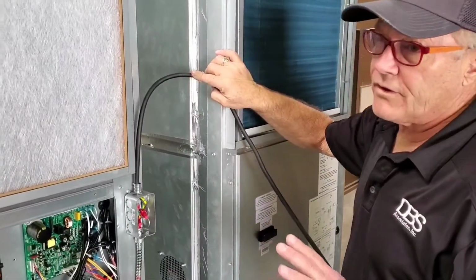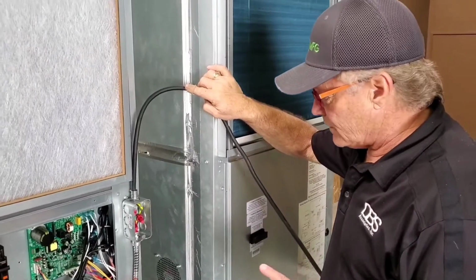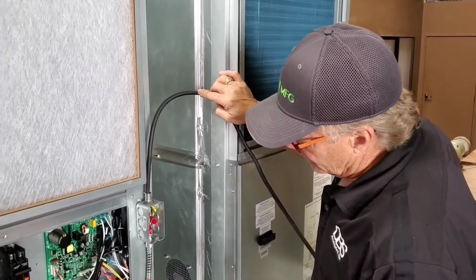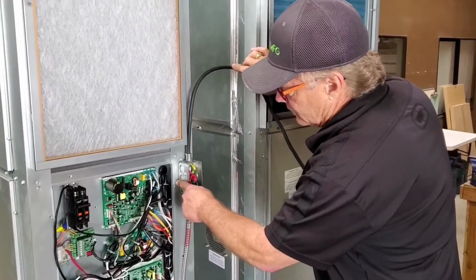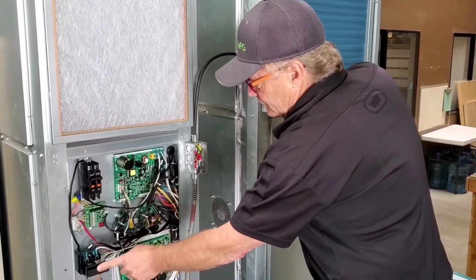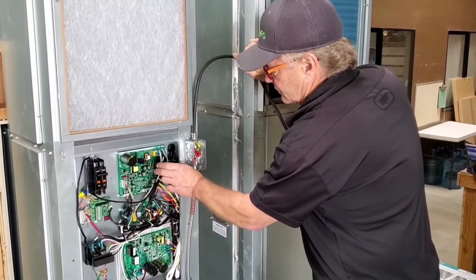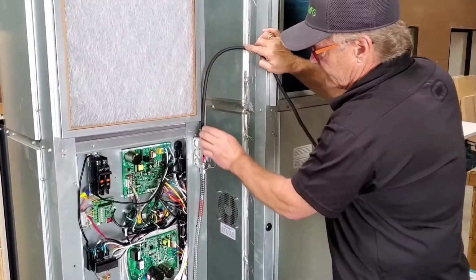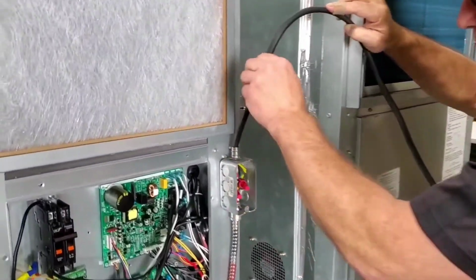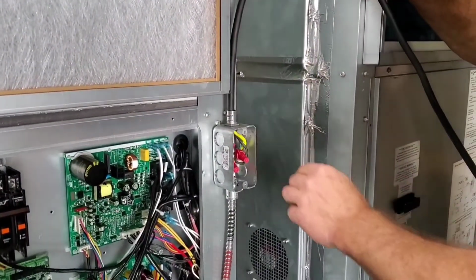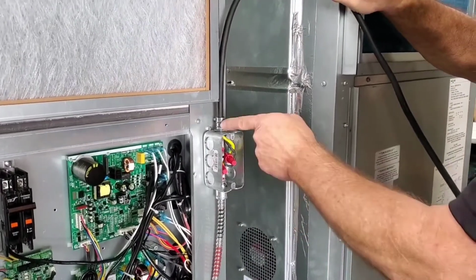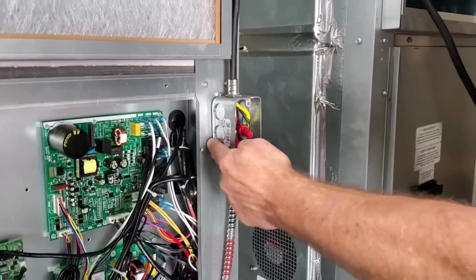Okay, the worst case scenario on a reinstall for this new unit is your First Company or York product is going to have a hole up here for the electrical. Their fused pole disconnect is in this location. So your wire and your steel flex is probably going to be short. We've just used SJ cord as a display unit, but you're normally going to have a steel flex coming in here tying into a connection similar to this.